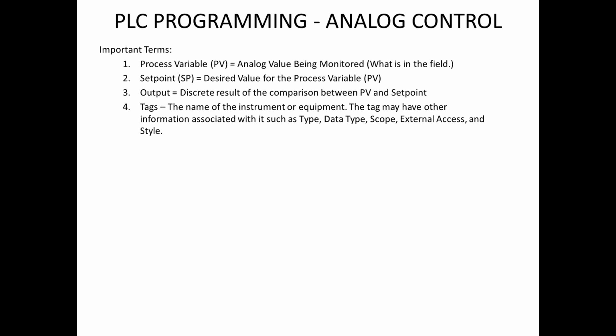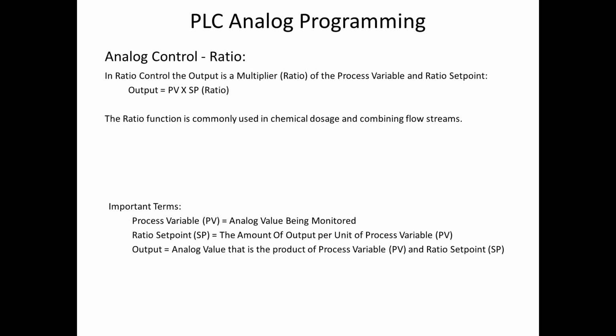I'm about out of time, so I'm not going to go into this very much, other than to tell you that there is an analog control, ratio control, which basically allows you to tell the PLC that, for example, for every million gallons coming in, I want to send so much dosage to the pump. You want the pump to pump so much, and it's a ratio. It's commonly used for dosage flow.